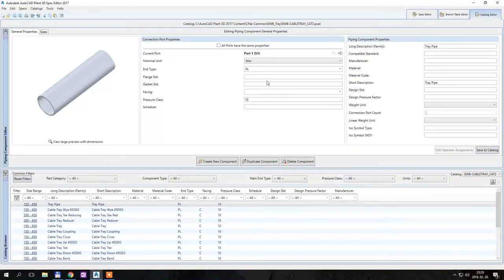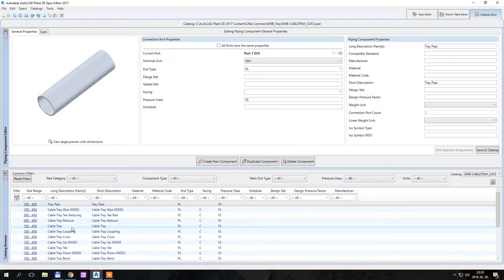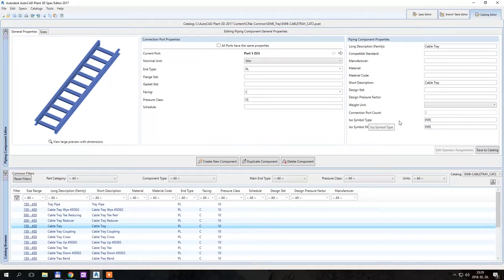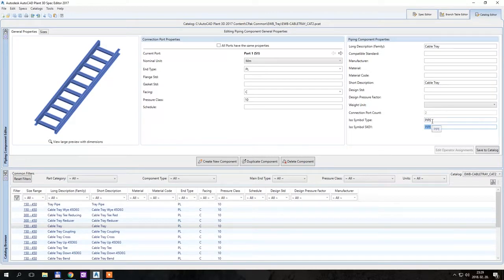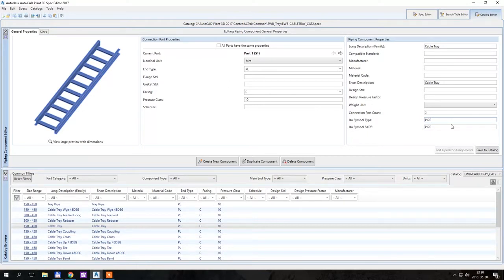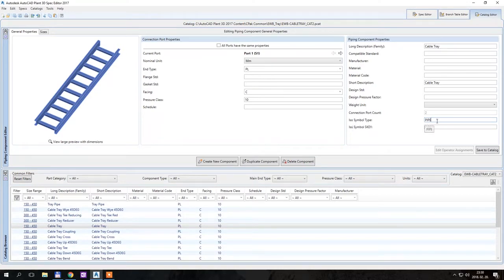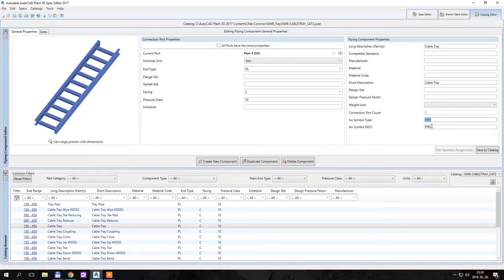So if you go to the spec editor and just select cable tray, you enter pipe here and there and you will be good to go. From this point onwards, Plant 3D will recognize the straight cable trays as pipes because the ISO symbol type is given as pipe and the SKEY is also pipe. So you just enter this to what you see here and then you won't have to bother with it in the 3D model.